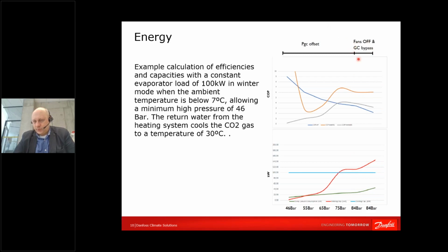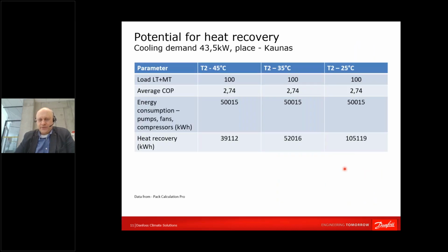Here, cooling engineers would probably discover what is happening in the cooling system when fans are off and the gas cooler bypass is turned to the relevant position. So you can see that the cooling capacity is staying. We are just increasing COP, so we are gaining extra. So there is no worry for people that we are pressing harder and turning the compressor harder. We're just making energy from the cooling machine. Therefore, we are saying that systems should be combined together for the best result.